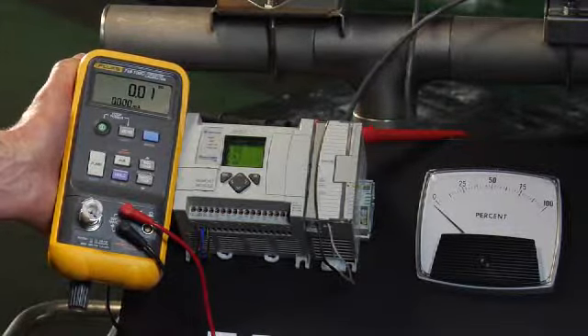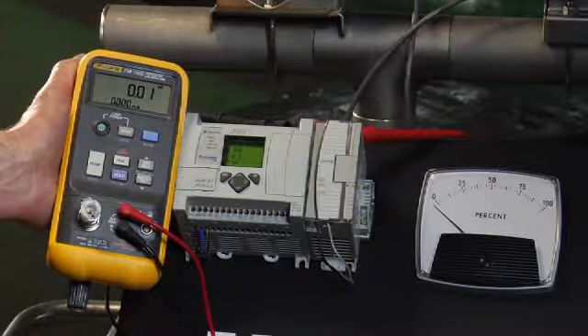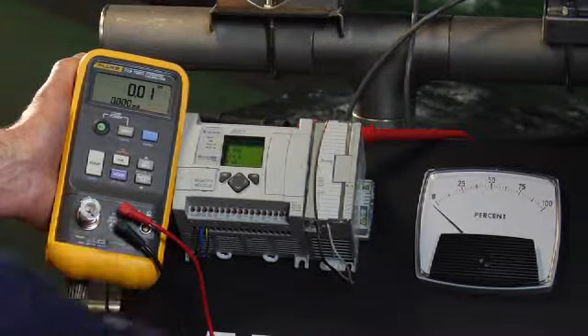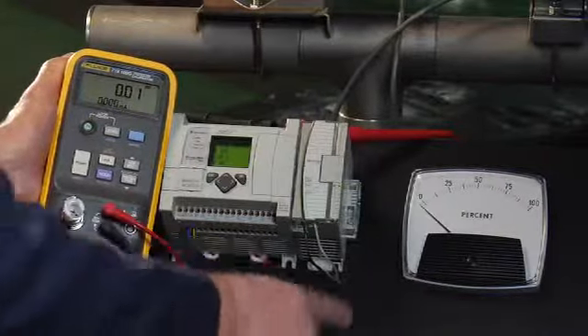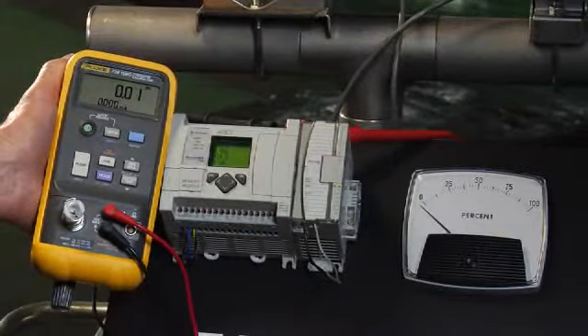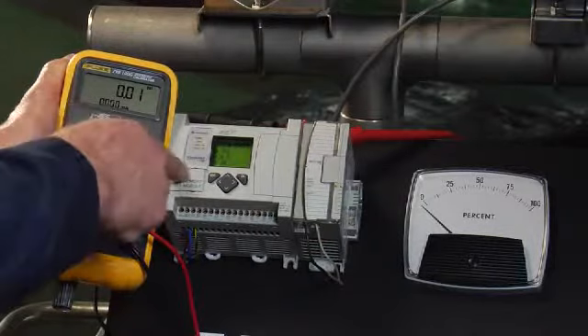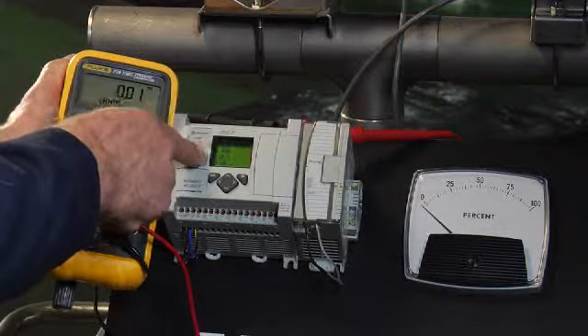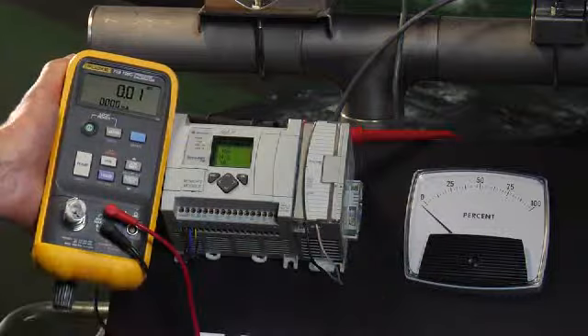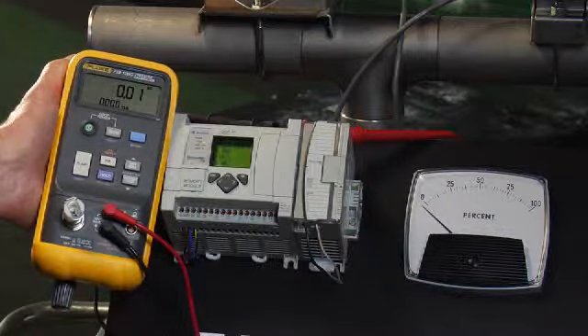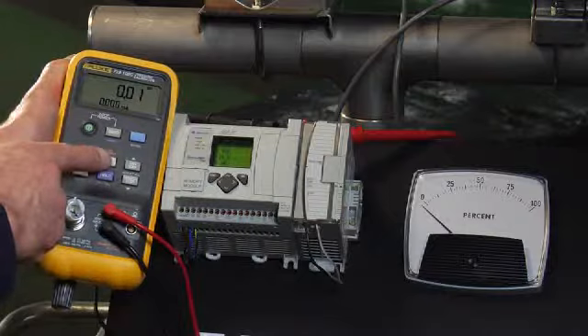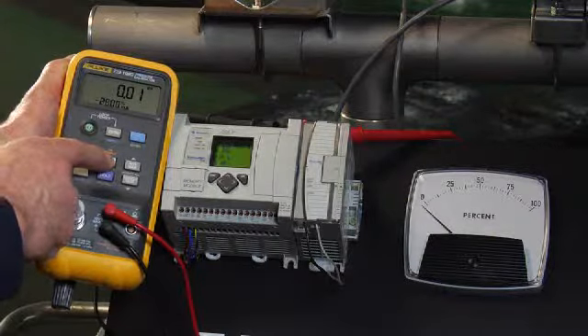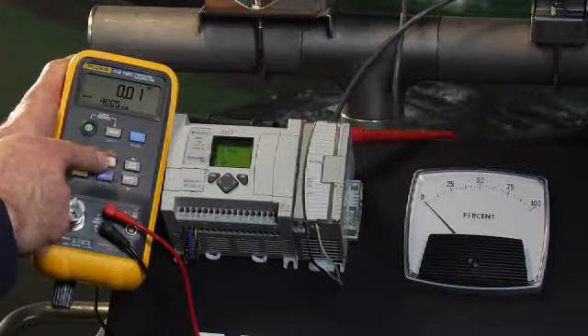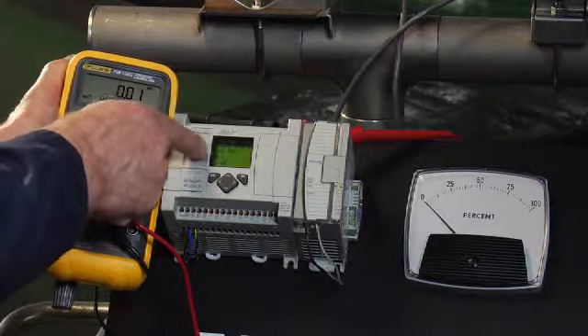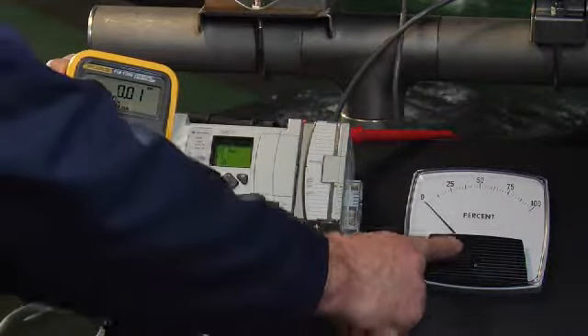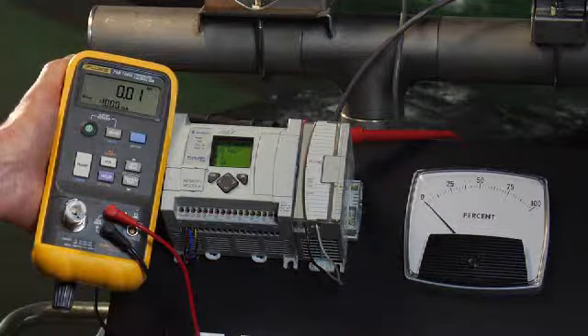milliamp I/O. In this example, we have the output of the 719 connected to the input of the PLC. The PLC output then drives the local indicator. So by sourcing a milliamp signal, we can drive the PLC, check for an indication, drive the output, and look for a local indication. To enact milliamp output mode, change the milliamp output to source, and you'll see we're sourcing 4 milliamps. The PLC is measuring 4 milliamps and 0% of span, and the local indicator shows 0%.